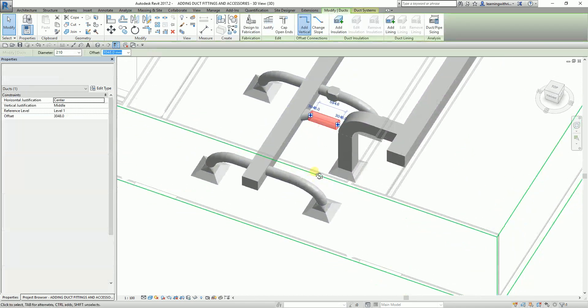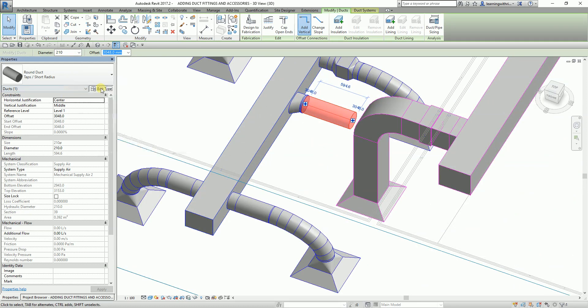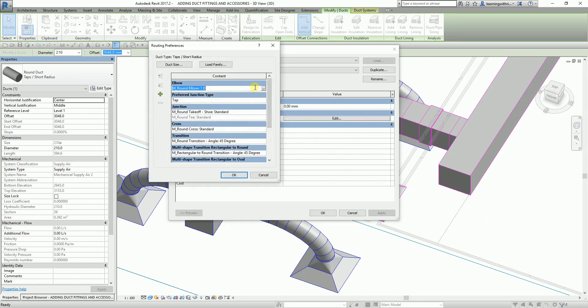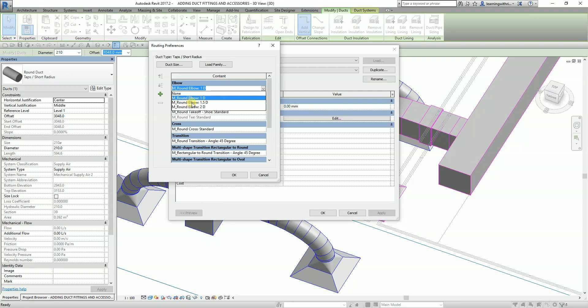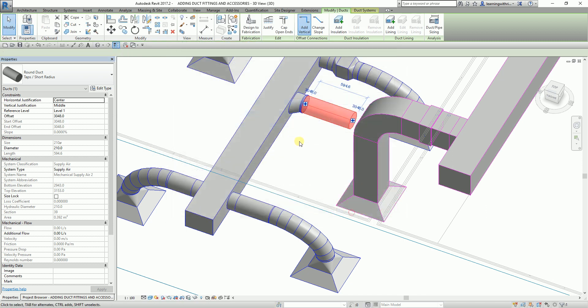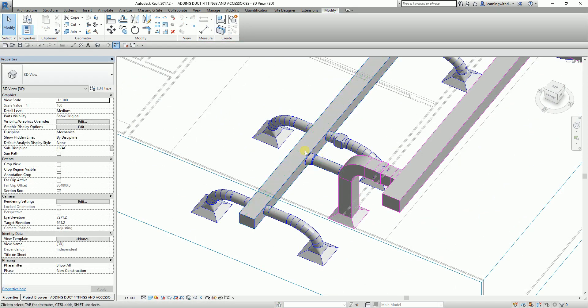You can also change elbow types in Routing Preferences — for example from M Round Elbow 1D to M Round Elbow 1.5D. For junctions there are three types available; selecting M Round Tee Standard will change what junction type is created when you draw new ducts with this duct type.